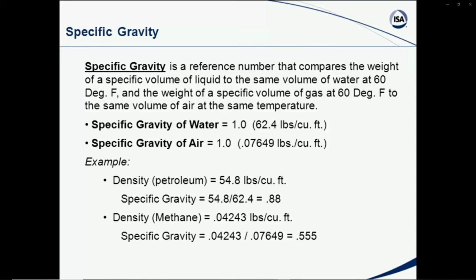Then also, we look at gases. The specific gravity of air is 1. Again, that's the weight in pounds per cubic foot of air at 60 degrees F, and then you'd compare other gases with it. For instance, methane has a density of 0.04243 pounds per cubic foot. Then if I compare that to air and divide that out, I'll get 0.555 as my specific gravity for methane.